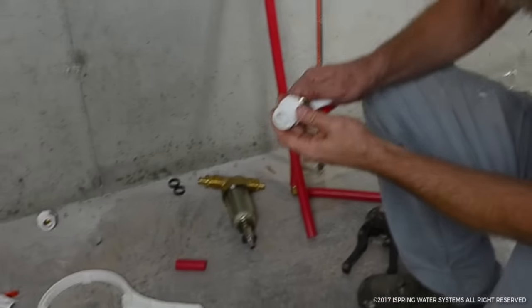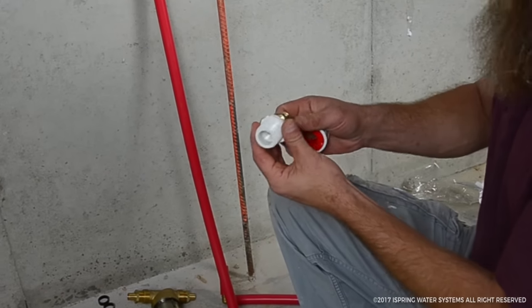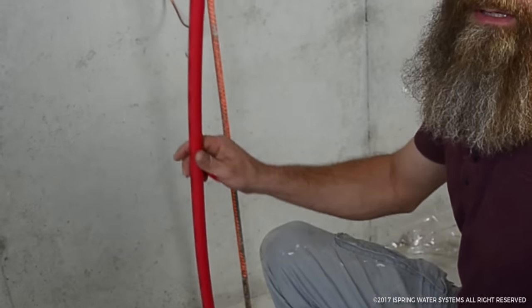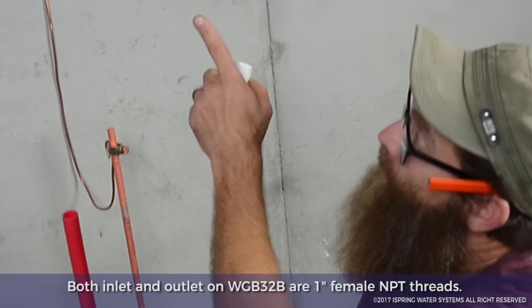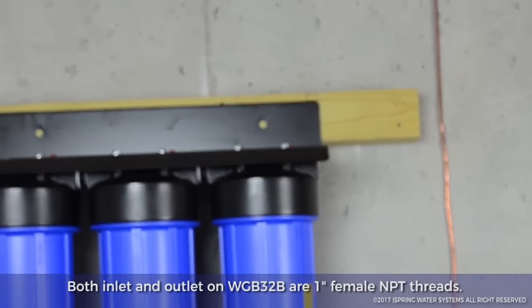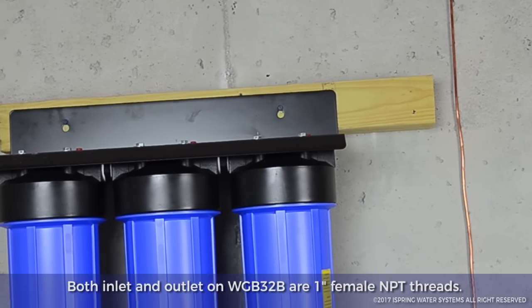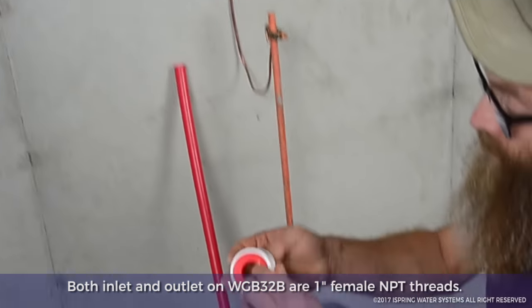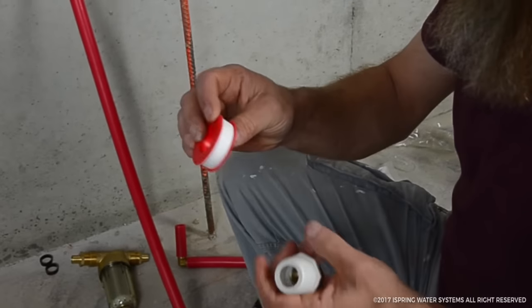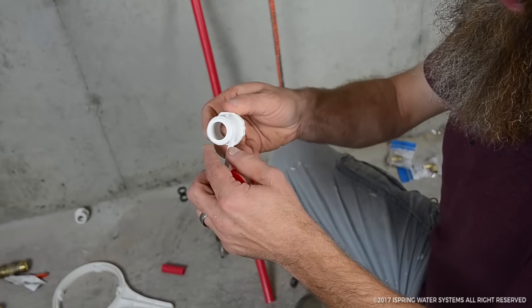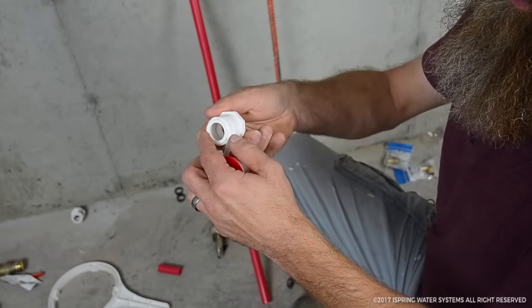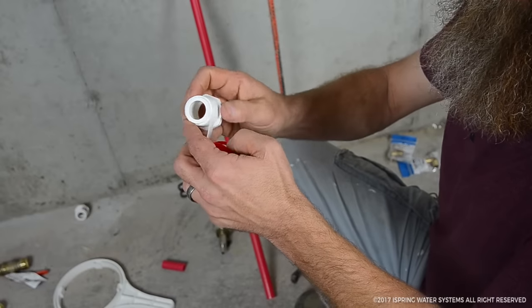The next thing we need to do is prep all our fittings. Since I have a three-quarter inch line and this has a one inch inlet, we have to reduce down to three quarters. So we have to use Teflon tape on everything. I always lay it on there in the direction that it tightens. I usually do about three times around.